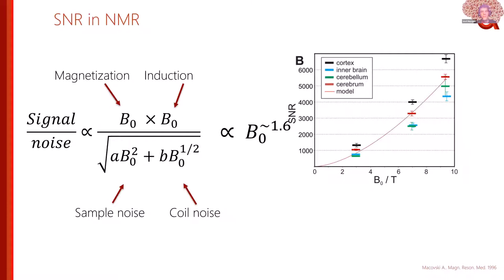We are all excited about high fields, and the promise is that you get a lot more SNR. SNR increases both because you get more magnetization and because the way we detect signal via signal induction also rises. This comes with the promise of a squared increase in SNR, though in practice — accounting for sample noise and coil noise — the actual increase of SNR with magnetic field is around 1.5 to 1.6.